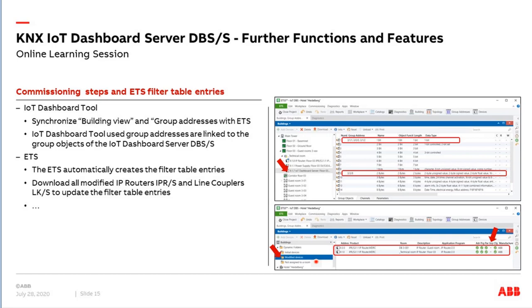The easiest way to download all IP routers or line couplers is to go to ETS and click the dynamic folder on top. When you click on it, you see the modified devices view by default. Clicking on modified devices shows on the right side a list of all devices that must be downloaded — for example, the IP router where the group address flag is now missing. You can start the download directly from this modified devices view.